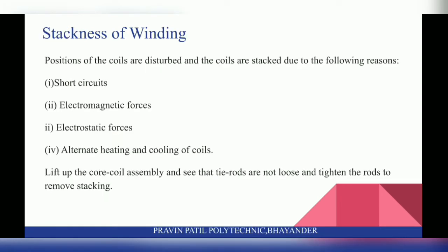Next is Stackedness of Winding. Positions of the coils are disturbed and the coils are stacked due to the following reasons: first is Short Circuit, second is Electromagnetic forces, third is Electrostatic forces, and fourth is Alternate heating and cooling of coils. Lift up the core-coil assembly and check that tie rods are not loose; tighten the rods to remove stacking.